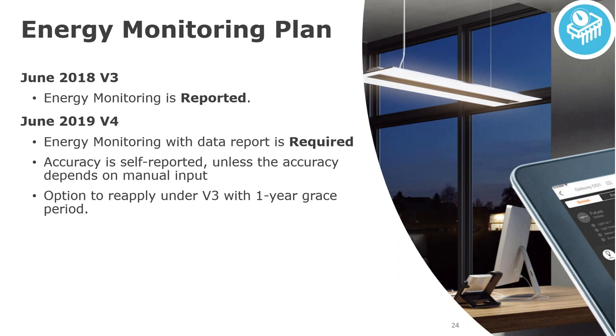A multi-year plan for energy monitoring was started in 2018, and we're following that plan to require energy monitoring along with an energy report in the form of either a CSV file or an API — application programming interface. We expect most products on the list to offer energy monitoring of some kind by June 2019, but remaining products will have a one-year grace period to remain listed under the old version 3.0 requirement.